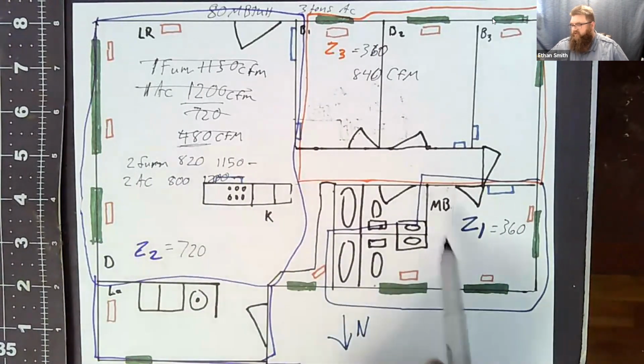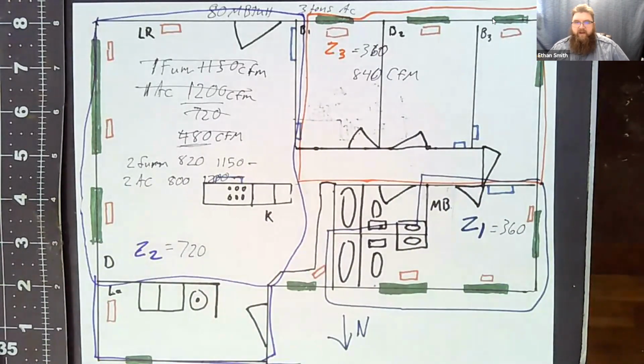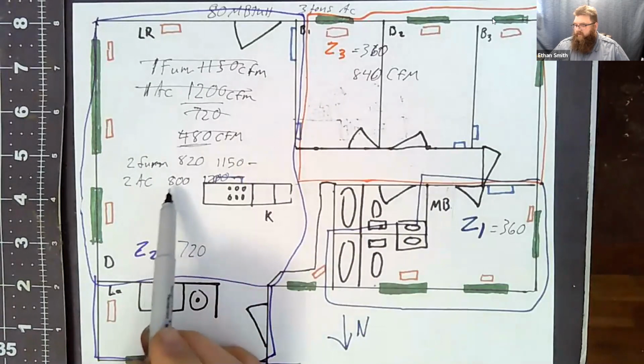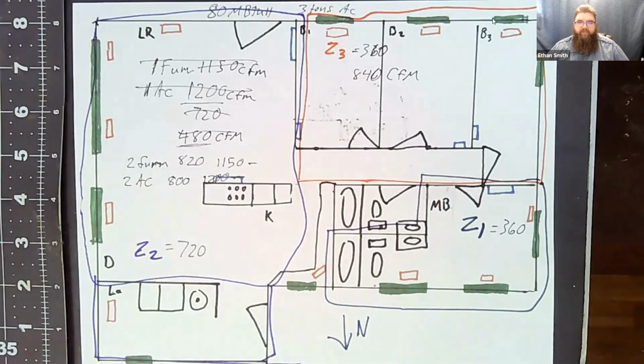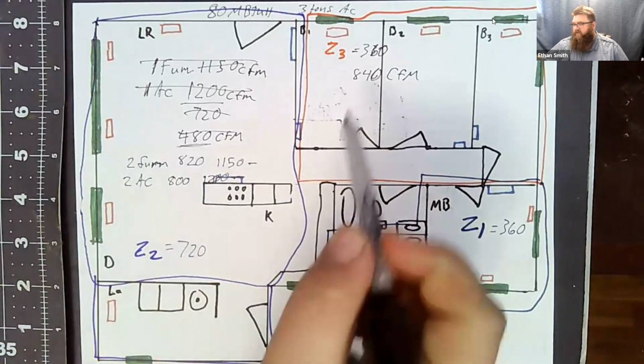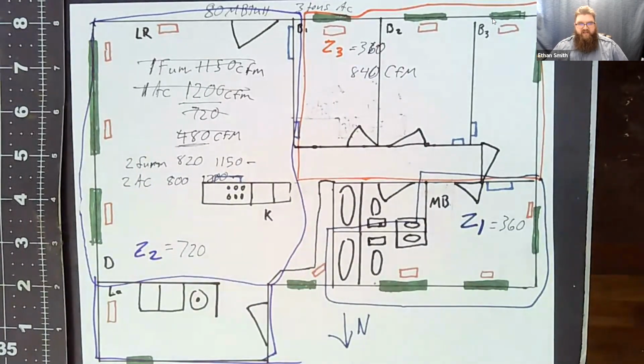Okay. But if we did this as a 2-zone rather than a 3-zone, I think we could make that work really well. Because then we got 2 zones that are going to make our minimum airflow requirements when either of them call. If we can get rid of excess air, we can make zoning work and work efficiently. Anytime we have an excess air problem, we've got to deal with it. That's usually going to cost us money in efficiency. Okay. So I'd say with a 2-stage piece of equipment, if we zone this, zone 1 and zone 3 together and zone 2 as it stands, we can make this work really, really well.